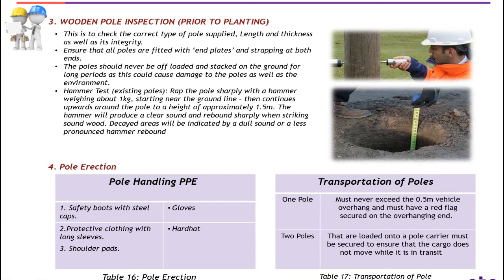Pole erection — PPE: Personal Protection Equipment for pole handling includes safety boots with steel cap, gloves, protective clothing with long sleeves, hard hat and shoulder pads. Transportation of poles: for one pole, it must never exceed 0.5 m vehicle overhang and must have a red flag secured on the overhanging end. For two poles loaded onto a pole carrier, they must be secured to ensure that the cargo does not move while in transit.